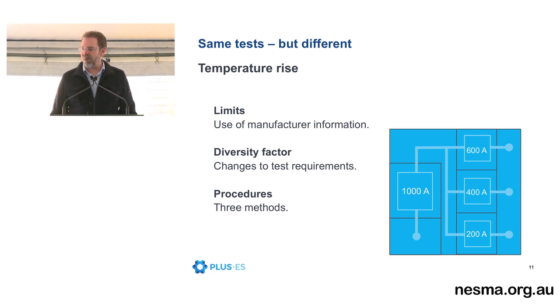Diversity factor is probably not as common a request as it used to be, because we would then have to go back and individually verify each outgoing unit can actually run at 100%. So that's a big change.